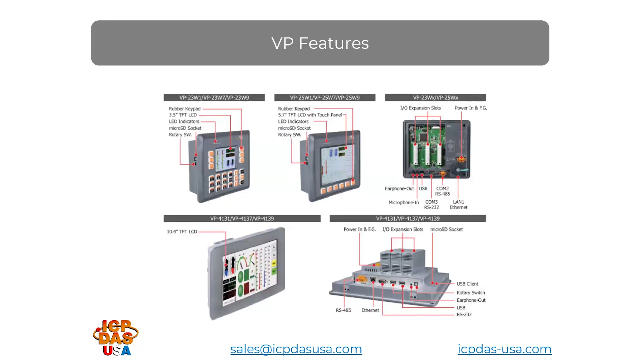The ViewPAC is basically a WP with an HMI built in. The touchscreen HMI can easily reduce the number of hardwired buttons and switches required for the control panel, and control the application using the same .NET or ladder program without needing an additional PLC. The VP can also multitask with its Windows operating system, and some models include expansion slots on the back to control I/O or communicate using its built-in serial and Ethernet ports to external equipment or expansion I/O racks.